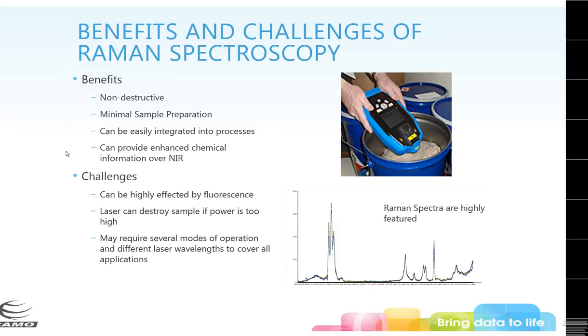Another benefit of Raman is that your spectra are very highly featured, so you can do some analysis directly on the raw data. You don't really need very much pre-processing for Raman data, which is fantastic because you're looking at fundamental vibrations here, as opposed to NIR where you're looking at overtones and combination bands. Looking directly at your data, things stand out more easily without serious pre-processing.